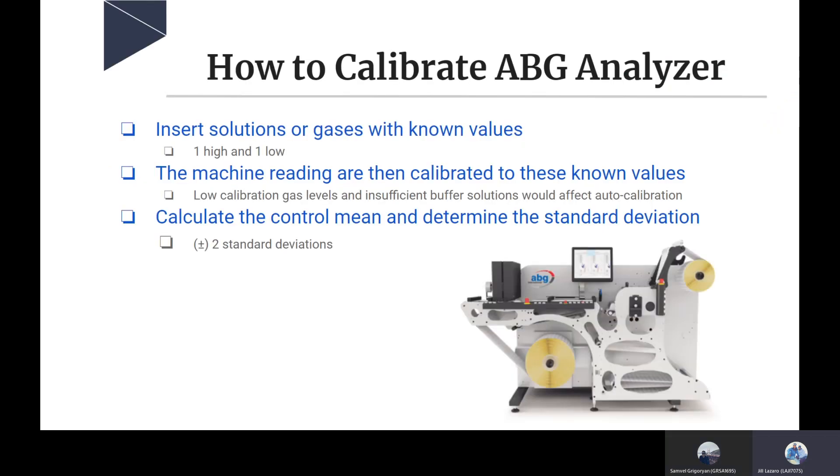Now we're going into how to calibrate an ABG analyzer. Calibration is specific to each different manufacturer and brand, so they'll have specific instructions. But in general, they work along the same kind of values. When we're calibrating the analyzer, we're doing it to make sure it's functioning correctly. How this works is that we insert a gas or solution with known values - one will be high and one will be low. The machine then reads and calibrates these known values. We can have some issues such as gas levels or insufficient buffer solutions that would affect calibration.